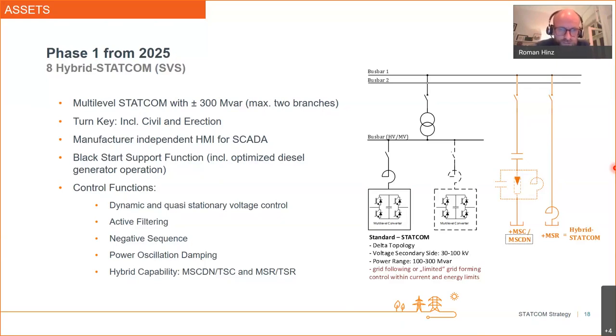In addition to the normal voltage control for the STATCOMs, we had some additional control demands, and maybe not everyone knows how you can also use a STATCOM. For example, you can add active filtering besides the normal voltage control. So you can select several voltage harmonics in the grid, and the STATCOM will inject a harmonic current to reduce the harmonic voltage. Fortunately, we have already implemented this in our current STATCOM, which I told you about before, at Lubmin. We did our FAT for this, and it works quite well. We are also looking forward to implementing this in these new STATCOMs.